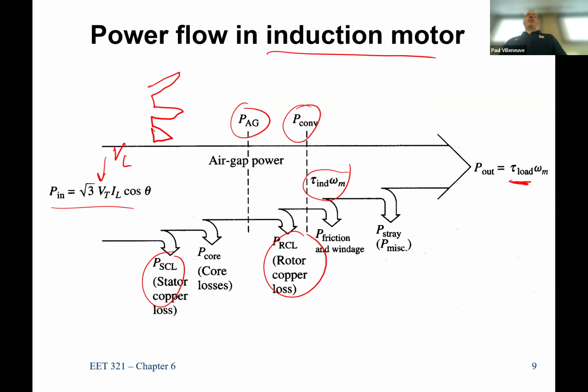This only works in certain applications. If you're in a mill processing area with water sloshing around and dirty fibers everywhere, that stuff gets sucked into the motor, makes it dirty, and kills its efficiency. So those are called enclosed, totally enclosed, or explosion proof motors, where no external air is allowed in. Those motors run very hot because there's no air exchange; all the heat exchange happens through the fins.